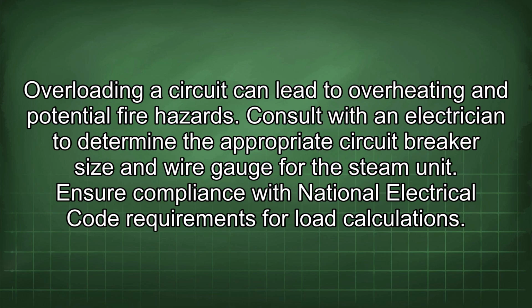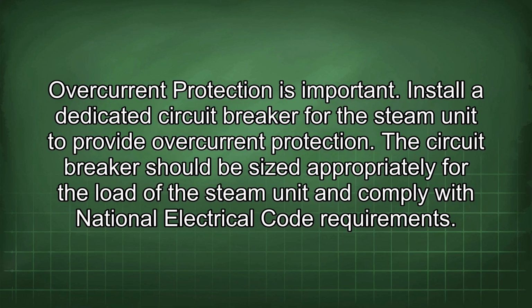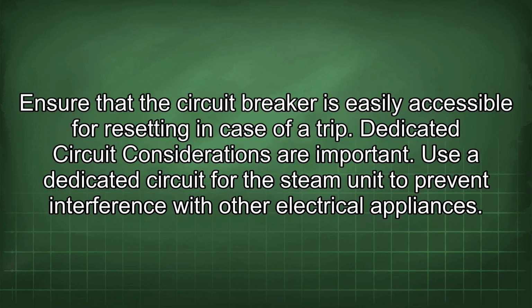Consult with an electrician to determine the appropriate circuit breaker size and wire gauge for the steam unit. Ensure compliance with National Electrical Code requirements for load calculations. Overcurrent protection is important. Install a dedicated circuit breaker for the steam unit to provide overcurrent protection. The circuit breaker should be sized appropriately for the load of the steam unit and comply with National Electrical Code requirements. Ensure that the circuit breaker is easily accessible for resetting in case of a trip.